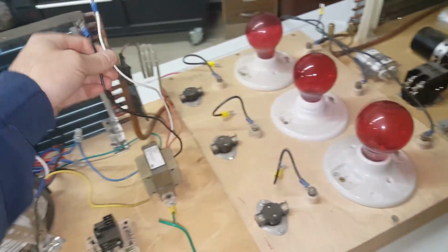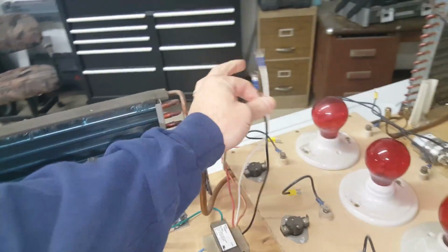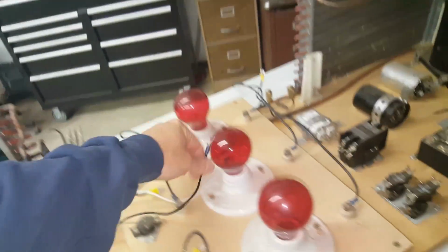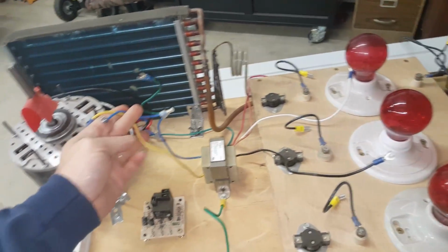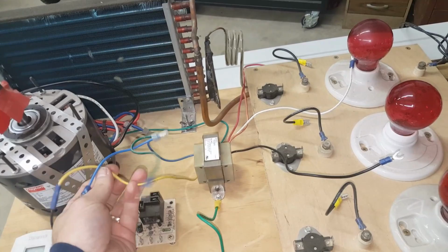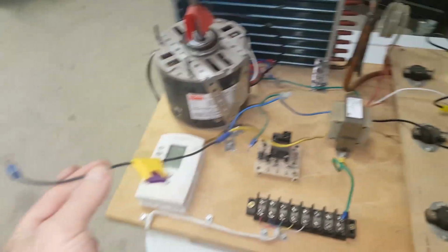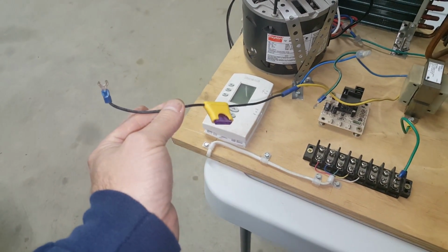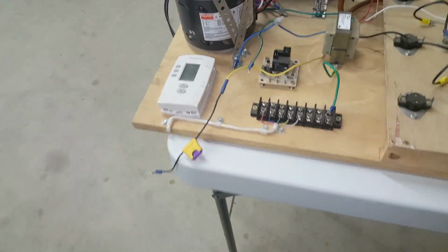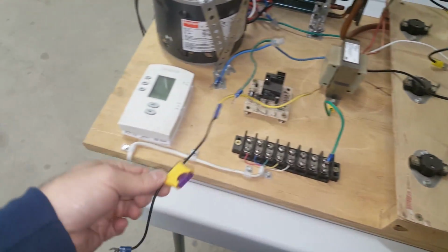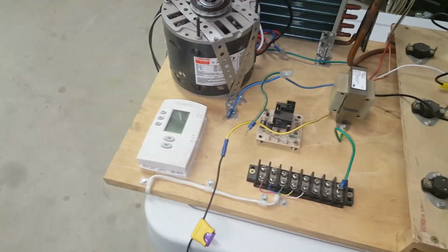Okay, we're back. The primary voltage is hooked up, simulating 240, but we're hooking up to 120. That's going to give us, I'm sorry, that's not going to give us 200. That's going to give us 24 volts on the secondary side. 24 volt hot with a fuse. Always put an inline fuse with your 24 volt hot. That'll save your transformer in case of a short.